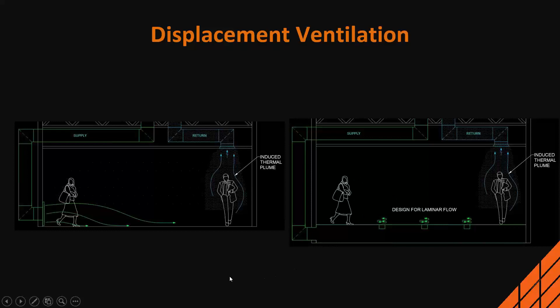We'd want laminar flow by the breathing zone, roughly 3 feet, so if you're sitting at your desk the air is moving a lot slower at that point. Again, we can induce that thermal plume and capture it. But these two approaches aren't something we can commonly apply to most of our buildings.